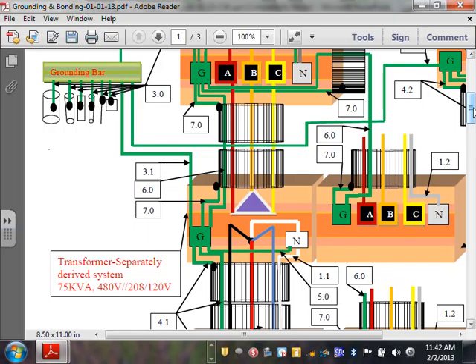Can't it hit the steel close by though? It doesn't have to go all the way back to the bus bar, right? Steel building, yes. Everywhere. Yes. A steel building, yes. But I see your point though. Can you take one and that will act as your equipment grounding conductor and your grounding electrode conductor, right? In this case, they're all going to the same point. It will be a grounding electrode conductor and equipment grounding conductor, because it's going all to the same point.